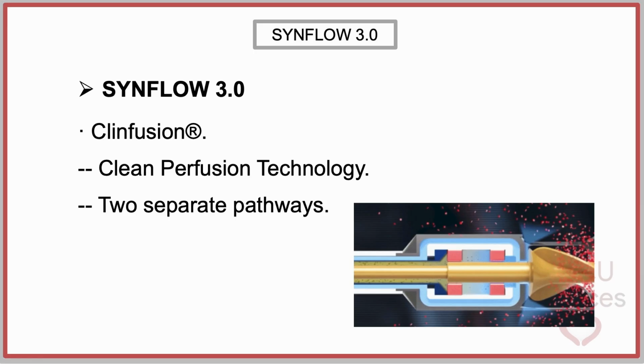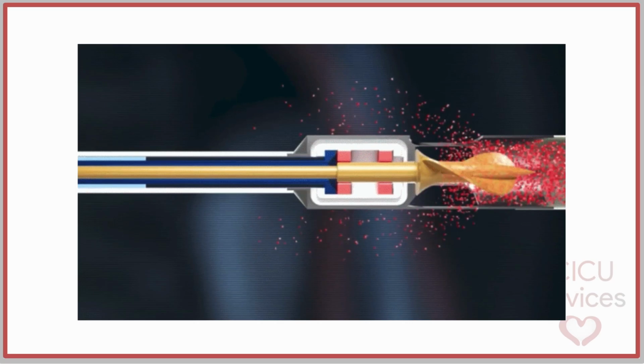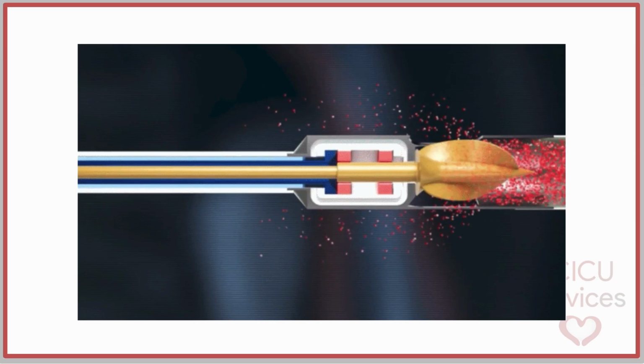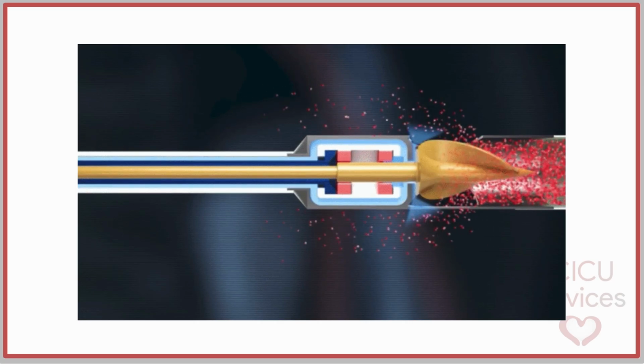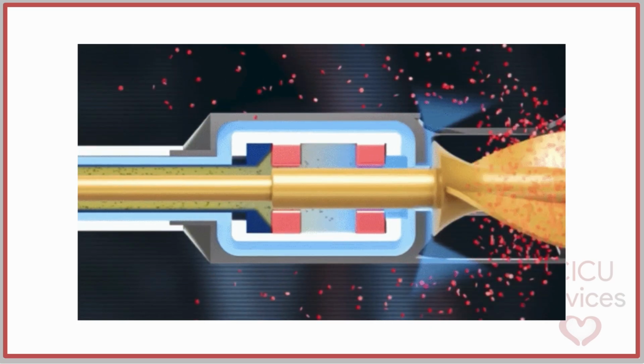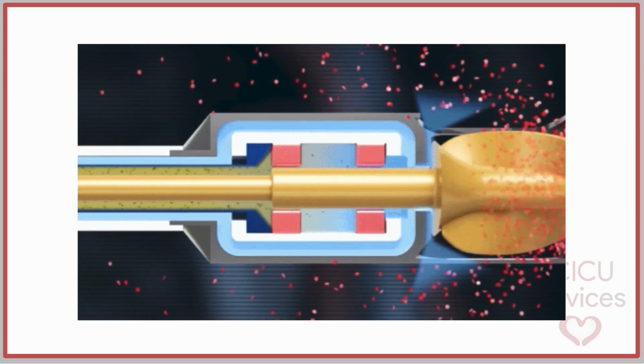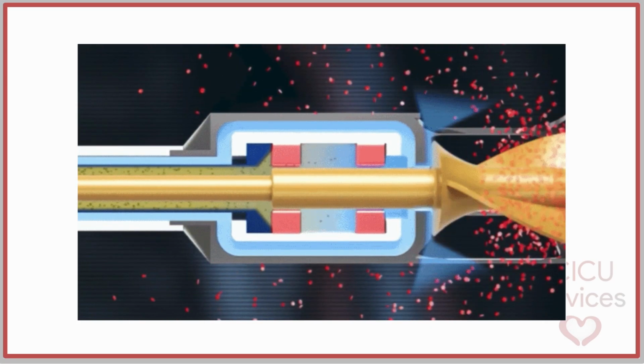into 2 separate pathways. One stream flows forward into the arterial circulation, creating a barrier that prevents blood from refluxing into the transmission system. The second stream circulates backward along the drive shaft toward the external console, continuously lubricating the mechanical components while carrying wear particles away from the patient.